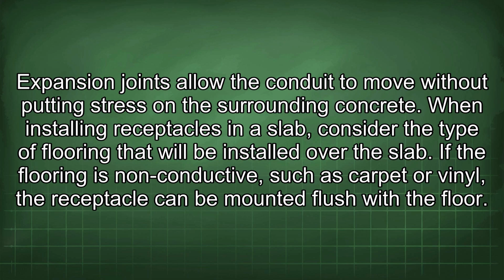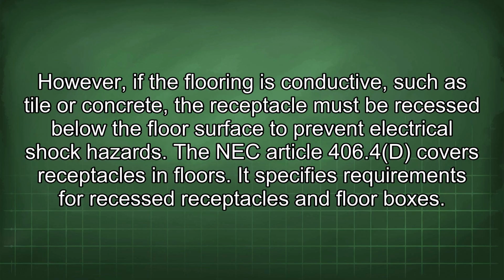When installing receptacles in a slab, consider the type of flooring that will be installed over the slab. If the flooring is non-conductive, such as carpet or vinyl, the receptacle can be mounted flush with the floor. However, if the flooring is conductive, such as tile or concrete, the receptacle must be recessed below the floor surface to prevent electrical shock hazards. The NEC Article 406.4d covers receptacles in floors. It specifies requirements for recessed receptacles and floor boxes.